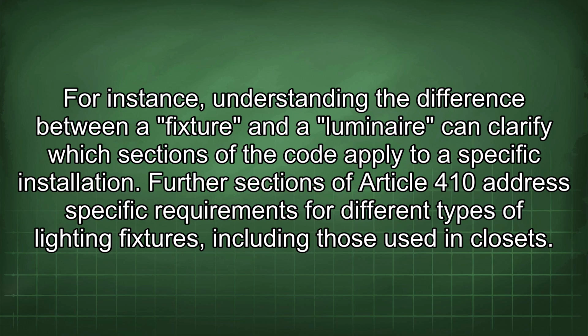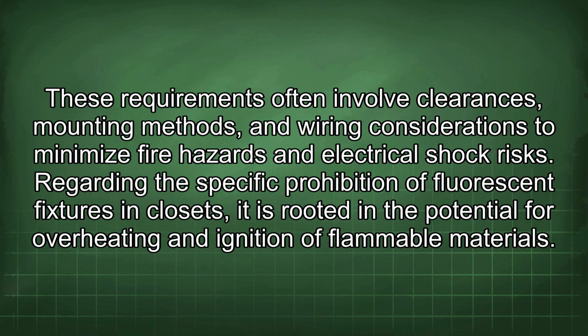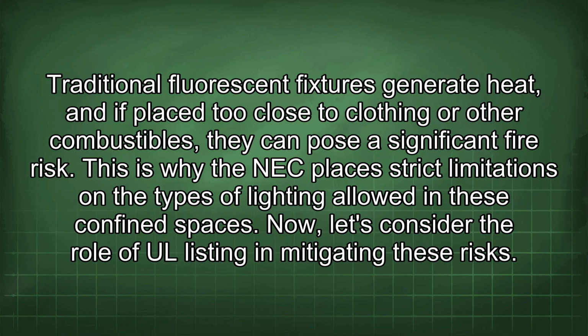Further sections of Article 410 address specific requirements for different types of lighting fixtures, including those used in closets. These requirements often involve clearances, mounting methods, and wiring considerations to minimize fire hazards and electrical shock risks. Regarding the specific prohibition of fluorescent fixtures in closets, it is rooted in the potential for overheating and ignition of flammable materials. Traditional fluorescent fixtures generate heat, and if placed too close to clothing or other combustibles, they can pose a significant fire risk.